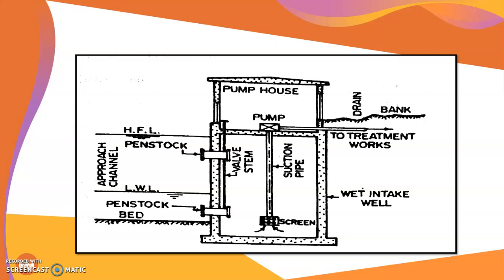The pump house is generally located above the highest flood level. The highest flood level is the water level which will be available in case of the highest flood. The pumps must be erected above that so that they can be protected even in case of the highest flood. The penstock at the upper level is operated for most of the duration in a year when the water is available above that level.